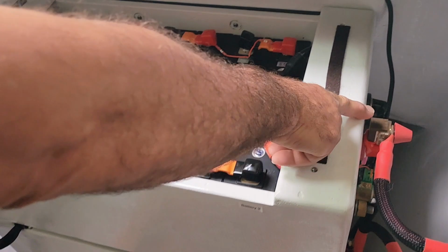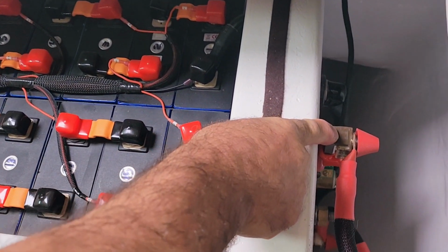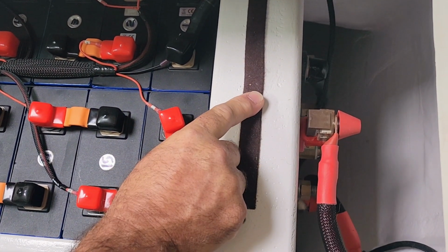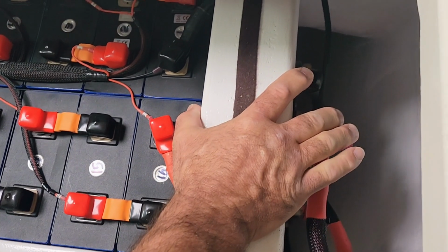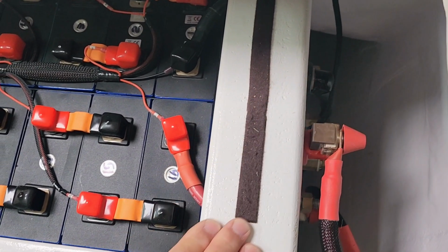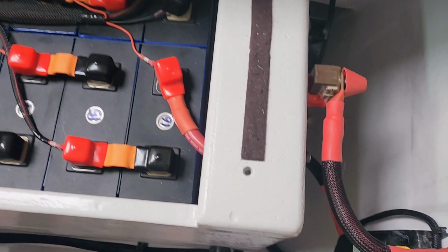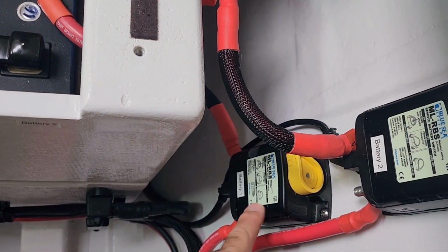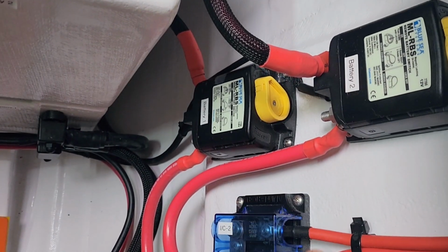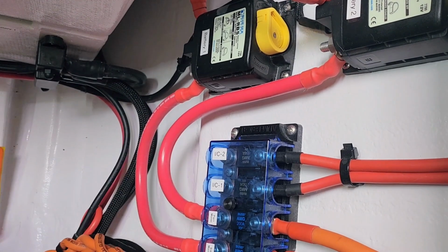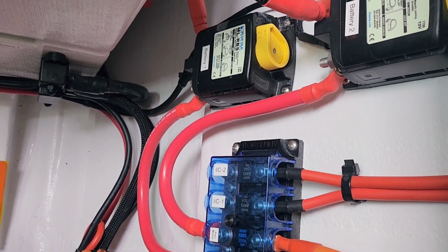Each battery has its own 300 amp fuse coming off the positive battery post. So they're fused at the battery post. And then once they go past the disconnect relays, each individual circuit is then fused appropriately for that circuit.